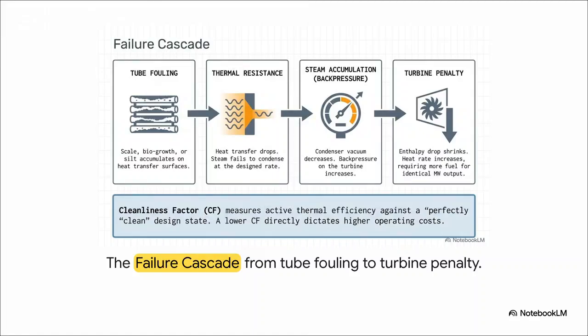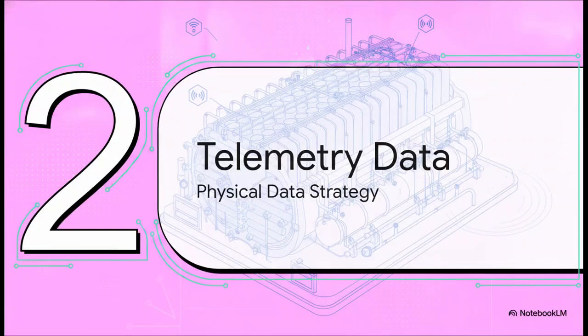The final result? The turbine penalty. The enthalpy drop shrinks, your heat rate shoots up, and suddenly you're forced to burn way more fuel just to maintain that exact same 600 megawatt output. The cleanliness factor we're calculating today measures our active efficiency against a perfectly clean state to stop this exact cascade from happening. All right, let's shift our focus from the theory to the reality on the ground.